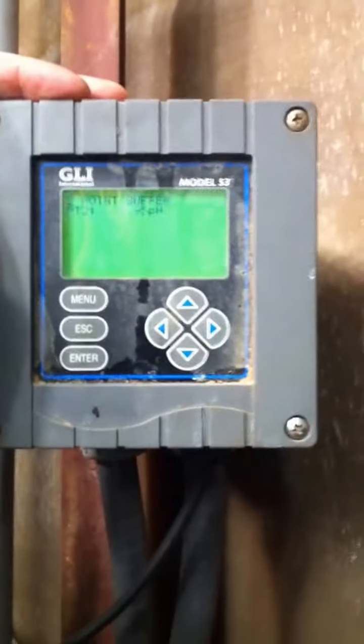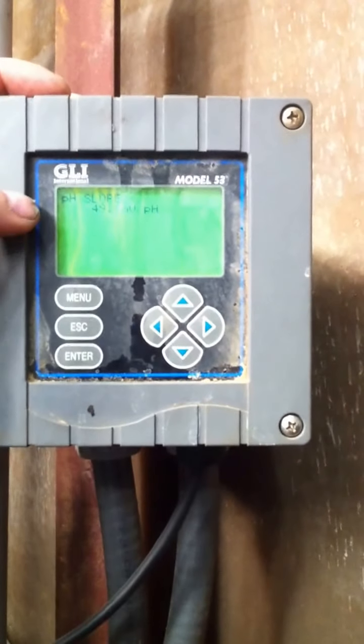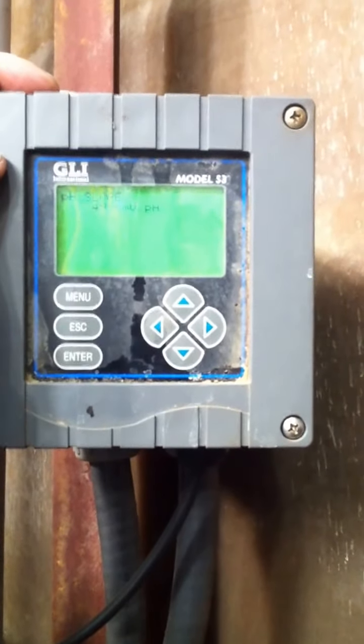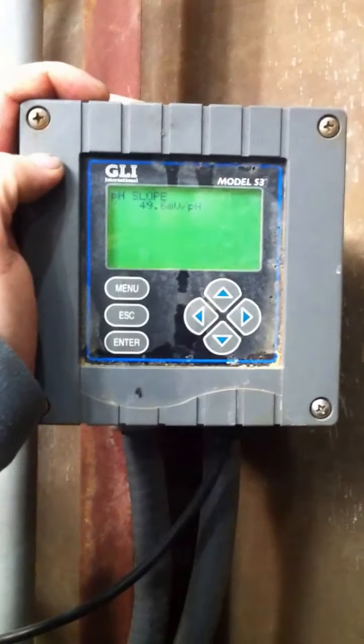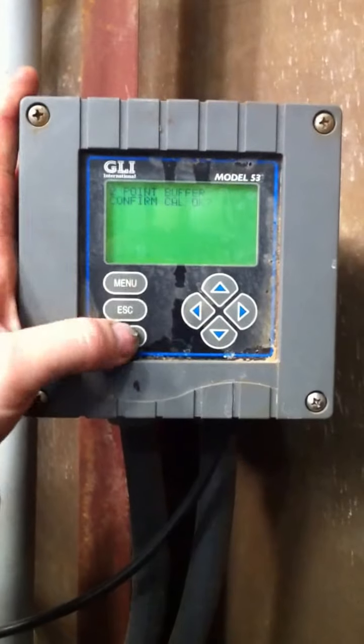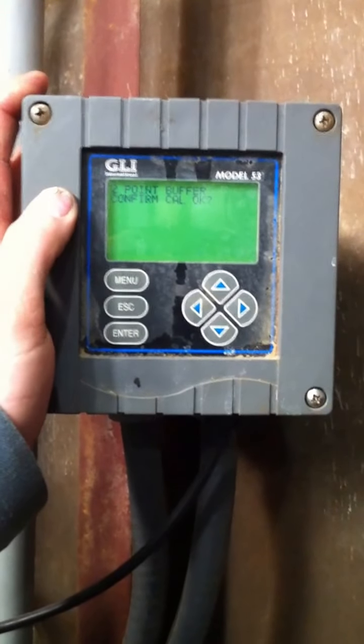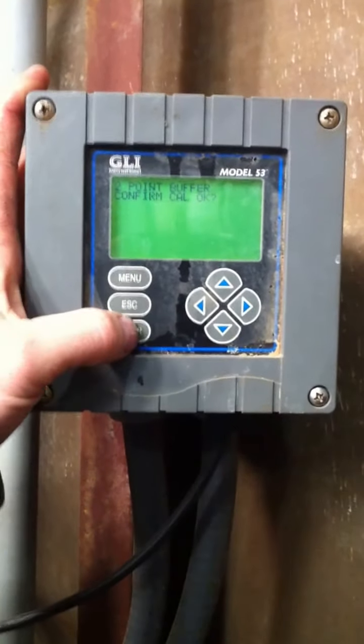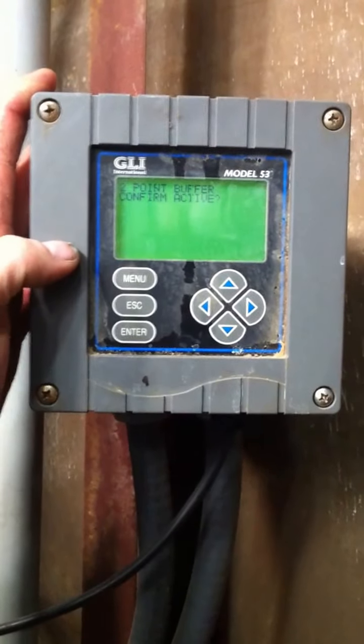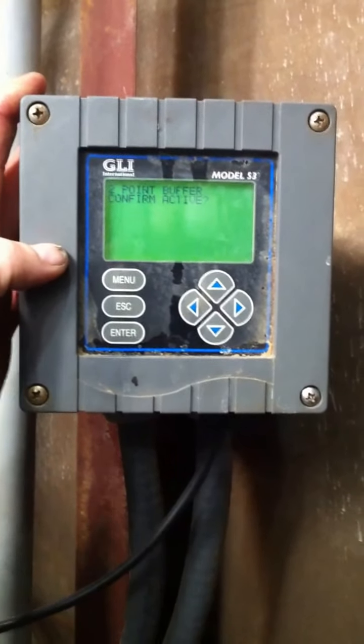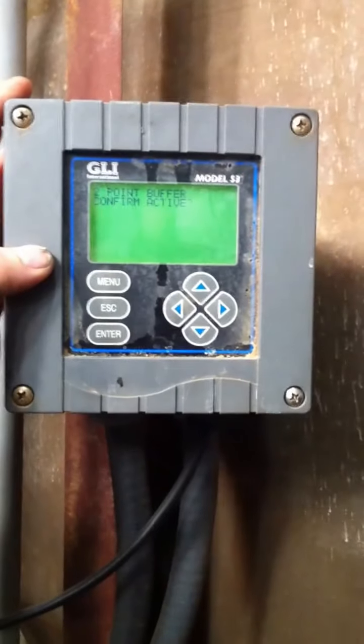At this point, it's saying point 2 is calibrated to a 9.95 pH. It gives the pH slope of 49.6 millivolts per pH. I'm going to push enter. It's going to ask confirm calibration OK. I do want to confirm it OK. I'm going to push enter, and then it asks to confirm active. Before I activate it, I'll remove the probe from the 10, bring it out, go ahead and rinse it off.